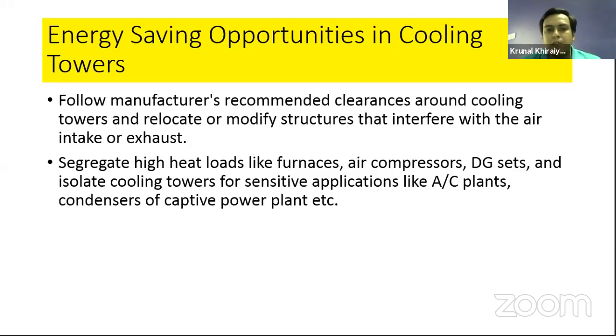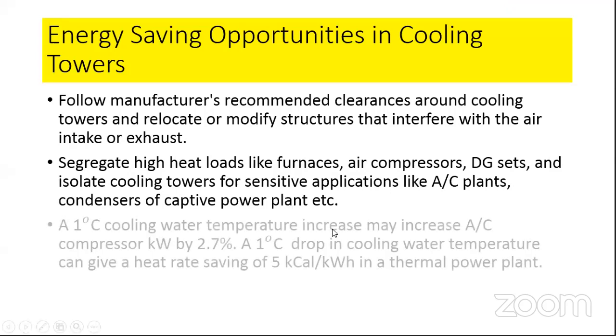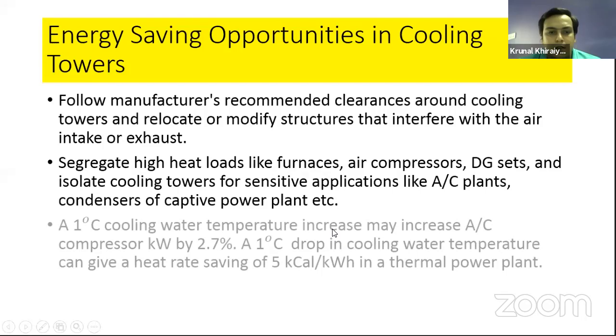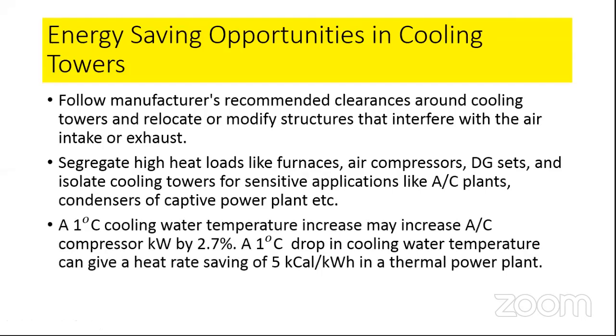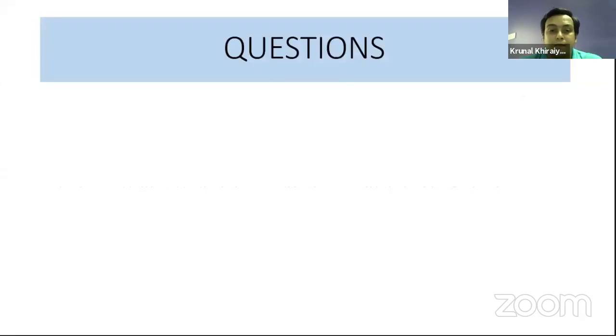It means merging of different activities, but it is not suggested, because if one cooling water temperature increases, it may increase the compressor power by 2.7 percent. It means a 1 degree drop in water temperature gives a heat saving of 5 kilowatt in power plants. So it is very important. You cannot merge; separate the different loads, because sometimes high load is there, sometimes low load is there.